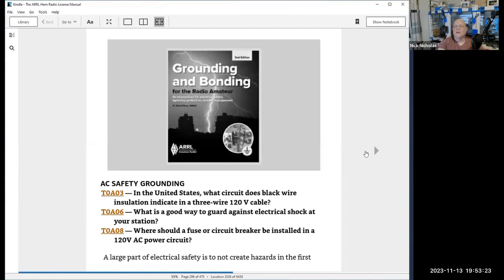The white wire is intended to carry current all the time whenever something's running. The ground wire is not. Ground fault detection circuits and so on detect when there's voltage on that line, and that's what protects your life. So you don't want to use the same wire out in the field, even though at the panel the ground and the neutral might be the same point. The wiring coming to and from is there to protect you by being separate. Likewise, all grounds should tie together, they should be bonded together.